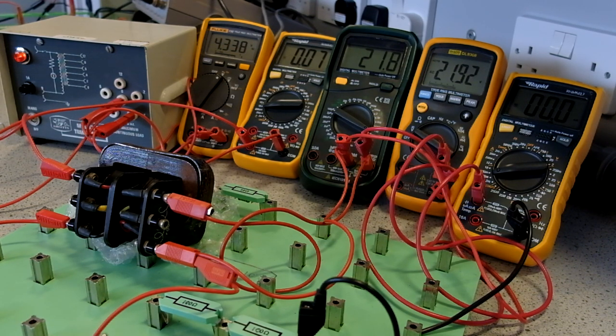The output coil has a resistance. So what we have here is internal resistance on the output circuit, and we have a voltage drop of approximately 1.9 volts through the output coil. That is what we would term a copper loss.